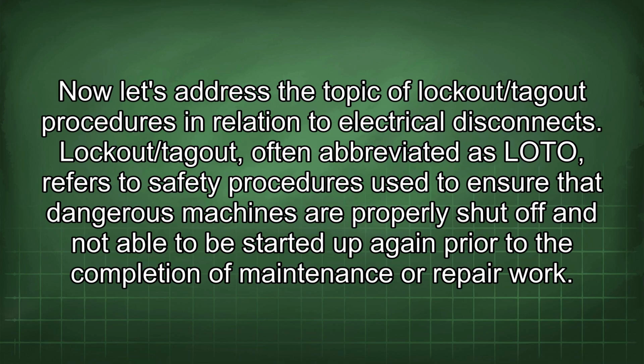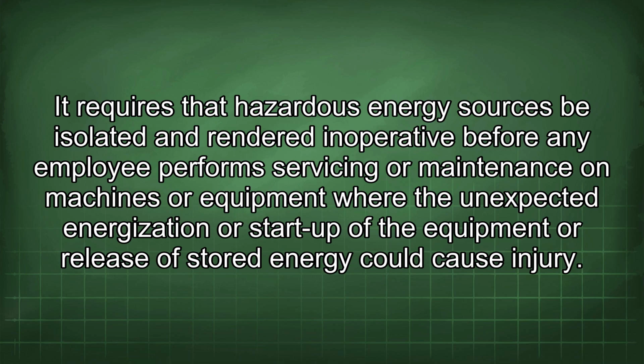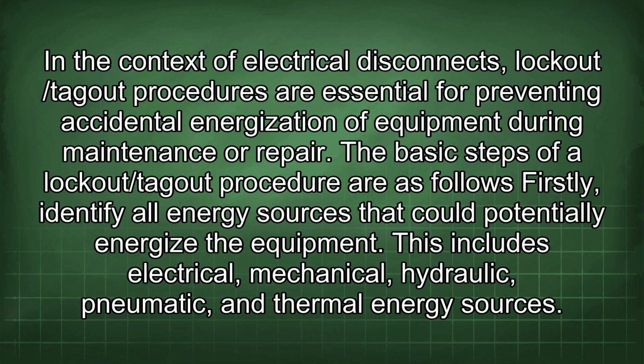Now let's address the topic of lockout/tagout procedures in relation to electrical disconnects. Lockout/tagout, often abbreviated as LOTO, refers to safety procedures used to ensure that dangerous machines are properly shut off and not able to be started up again prior to the completion of maintenance or repair work. It requires that hazardous energy sources be isolated and rendered inoperative before any employee performs servicing or maintenance on machines or equipment where the unexpected energization or startup of the equipment or release of stored energy could cause injury. In the context of electrical disconnects, lockout/tagout procedures are essential for preventing accidental energization of equipment during maintenance or repair.